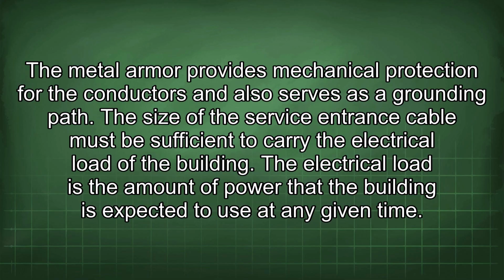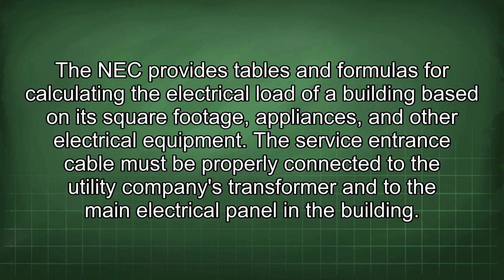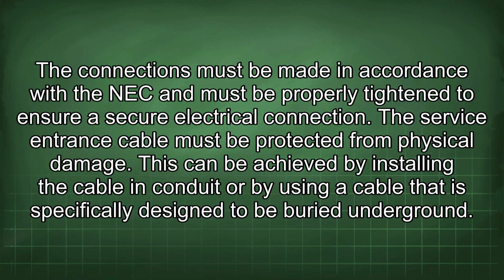The size of the service entrance cable must be sufficient to carry the electrical load of the building. The electrical load is the amount of power that the building is expected to use at any given time. The NEC provides tables and formulas for calculating the electrical load of a building based on its square footage, appliances, and other electrical equipment. The service entrance cable must be properly connected to the utility company's transformer and to the main electrical panel in the building. The connections must be made in accordance with the NEC and must be properly tightened to ensure a secure electrical connection. The service entrance cable must be protected from physical damage.